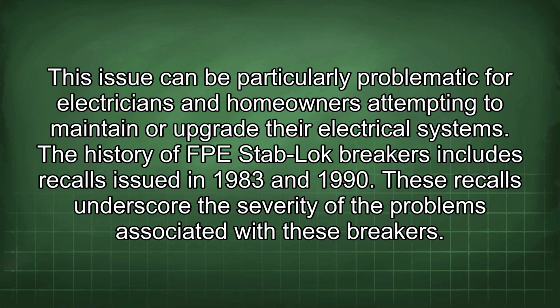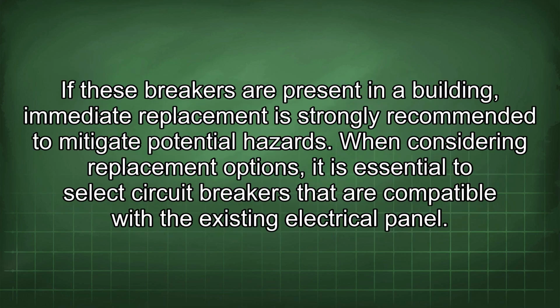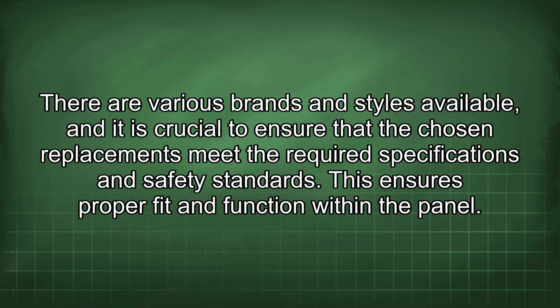The history of FPE Stab-Lok breakers includes recalls issued in 1983 and 1990. These recalls underscore the severity of the problems associated with these breakers. If these breakers are present in a building, immediate replacement is strongly recommended to mitigate potential hazards. When considering replacement options, it is essential to select circuit breakers that are compatible with the existing electrical panel. There are various brands and styles available, and it is crucial to ensure that the chosen replacements meet the required specifications and safety standards. This ensures proper fit and function within the panel.